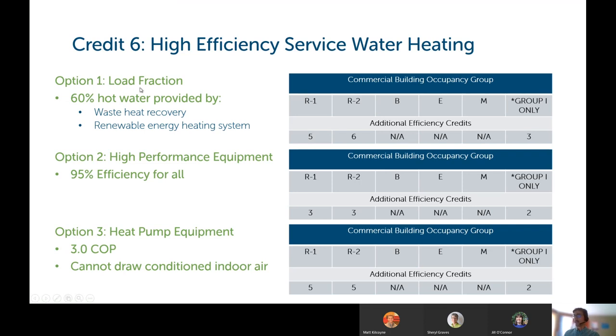So the first option is load fraction, where 60% of the hot water is provided by waste heat recovery or a renewable energy heating system. So if you follow that, you can get these credits associated here. Option two is high performance equipment. If all the heating equipment is 95% efficient or higher, that's for fuel burning equipment, then you can get these credits here. And option three is heat pump equipment that has 3.0 coefficient of performance. And you also must make sure you're not drawing the air for that heat pump from the conditioned indoor space. The only way you can do that is if it's exhausted air from the building.